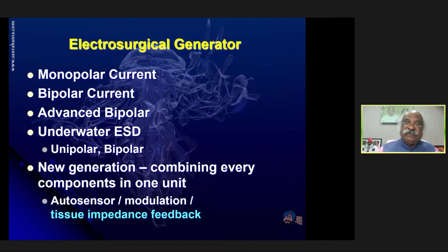Monopolar. From the beginning, I'm telling you that monopolar is a misnomer, because all electrical circuits must technically be bipolar, since a circuit must be completed. The word monopolar, meaning with one pole, is not possible. Everything is bipolar, because the electric current oscillates from the electrosurgical generator to the electrode, to the surgical site, through the patient's body into a dispersive or return electrode, and back to the generator. So the circuit is completed.